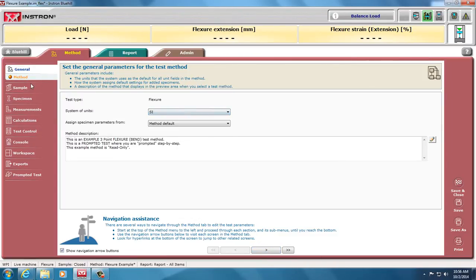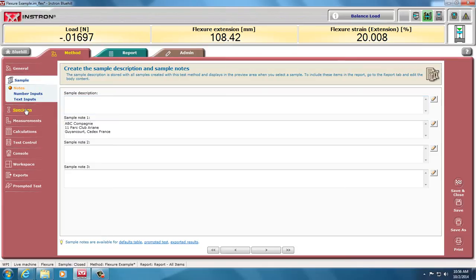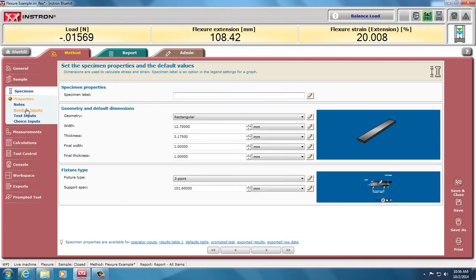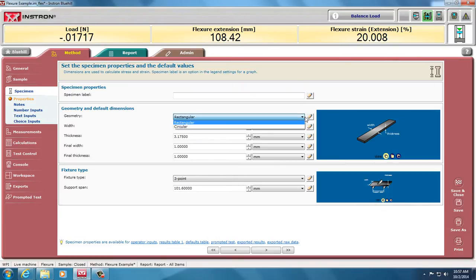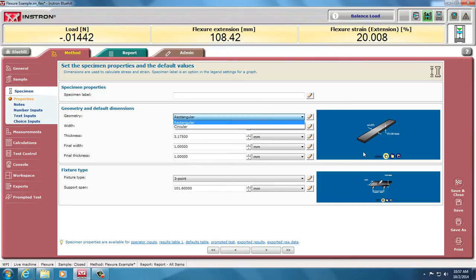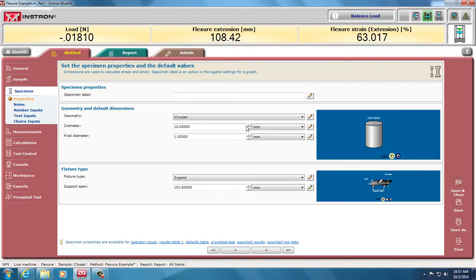I set my units as usual. I could set other sample properties and text inputs. My specimen, now here's where it becomes different than doing a uniaxial test. Here, we can pick two different geometries, rectangular or circular. Because the moment of inertia is involved, not just the area, it is important that you define the width and thickness correctly. The thickness is the vertical direction, the direction of loading, and the width is transverse to that. I'm going to pick circular because I have a circular dowel in my machine.